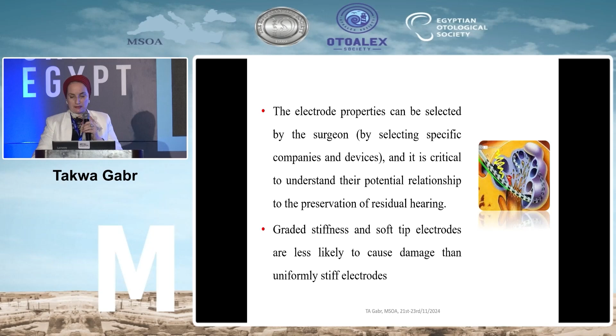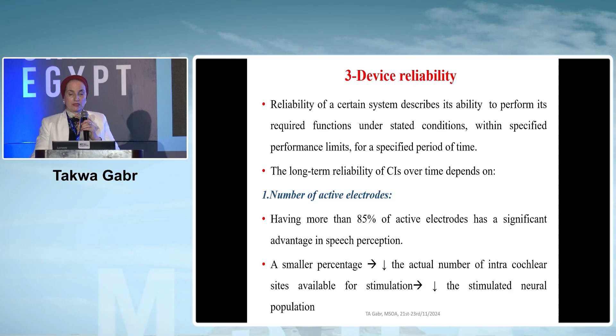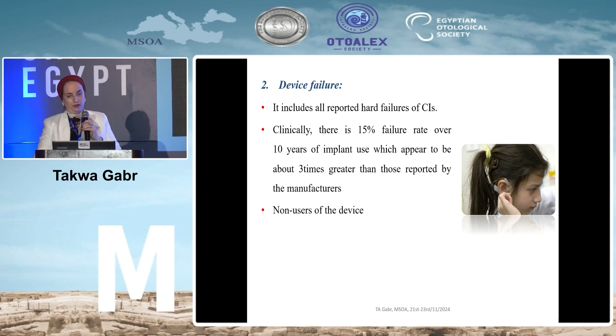The device reliability. This means the reliability of a certain system describes its ability to perform its required function under stated conditions within specified performance limits for a specified period of time. The long-term reliability of the cochlear implant depends on the number of active electrodes inside the electrode array, where if they exceed 85% of the electrodes, it will give good results because they indicate sufficient stimulation of the neural population. Reliability also is related to device failure, which includes cases with non-use of the device. So the clinical number exceeds what is being reported by the manufacturer for this cause.